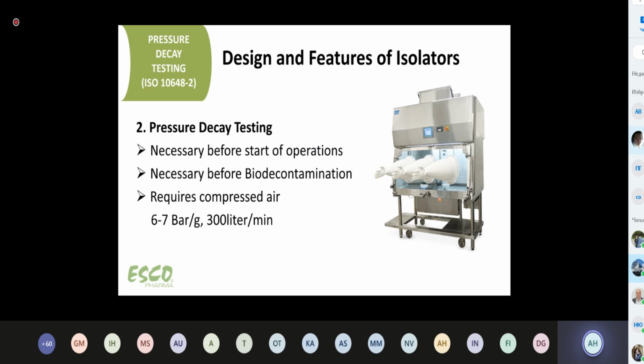Okay, so we come back here to this feature, pressure decay testing. It looks something like this. You have to do it before you start work. You have to do it before you biodecon. And what is the requirement? You need compressed air. You need 6 to 7 bars of pressure, 300 liters per minute of compressed air. So ask the customer, do you have compressed air in your facility? If the answer is no, no problem. ESCO can provide a built-in air compressor, of course, with an additional fee.